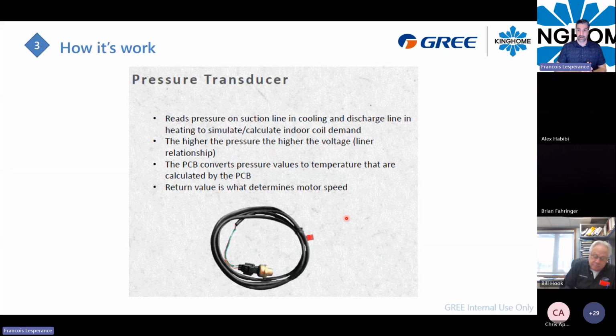And in heating mode, well, the same pipe will be used for the discharge pressure. So the pressure transducer in heating mode can manage the amount of pressure going out from the compressor. So by using its algorithm, it can manage the capacity demand for the compressor, and moving forward, it can increase or decrease the compressor frequency by knowing this information. So it's not an on-off compressor. It will vary its capacity demand.